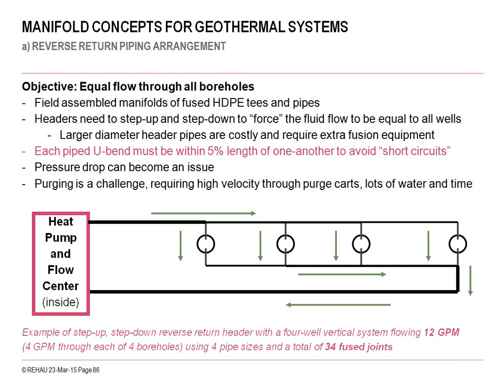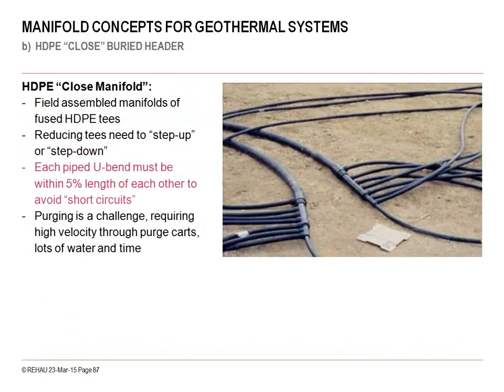And you want to have the lengths of those boreholes in the piping material to be within about plus or minus 5% lengths of each other to minimize any short circuiting in the flow between all four of those boreholes. Just a sidebar here, in this particular circuit of 4 boreholes, you have in the area of about 34 welded or fused connections with the HDPE pipe. And it's just showing you some illustration of the headering with that fusion of the tails, if you will, from the boreholes with the HDPE pipe. When you're purging this type of a reverse return, you're purging the entire circuit of however many boreholes are on that circuit.